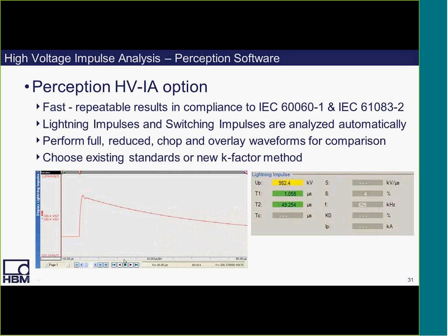Here again, the perception software provides complete control, display, and automated analysis and reporting capabilities. And when you include the HVIA analysis option, which is the high voltage impulse analysis, it provides fast and repeatable results in compliance to IEC international standards, including UP, T1, T2, and so on, as you can see in the result window on the right. Now, lightning impulses as well as switching impulses are analyzed, and the characteristic parameters are calculated automatically.